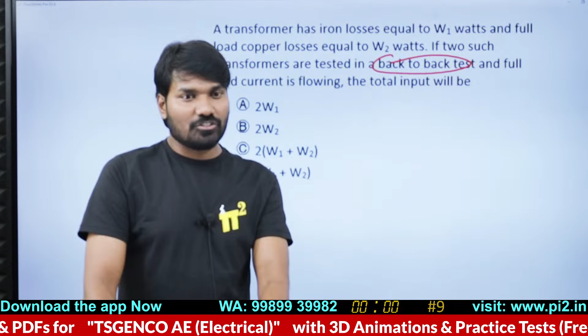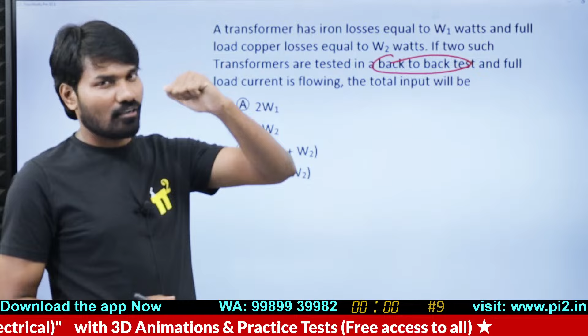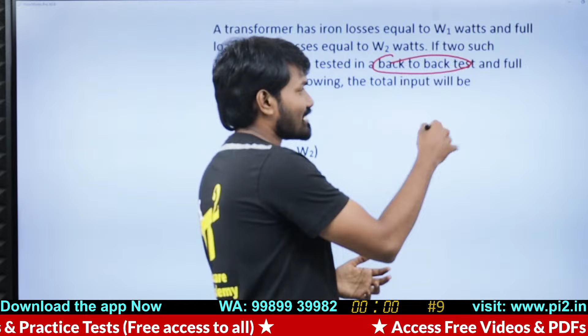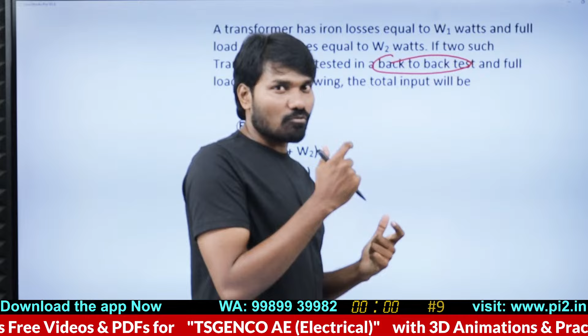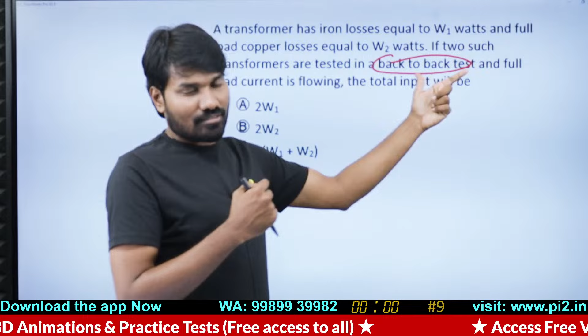Let's get back to our question series. So this is also called a heat run test, and there's a reason why it's called that. OC test and SC test have some limitations, they're indirect methods of testing. Back-to-back test is also indirect, but it overcomes the disadvantages, because heat generation in the transformer cannot be found out using OC-SC test. That's why we use the back-to-back test, popularly called the Sumpner's test.